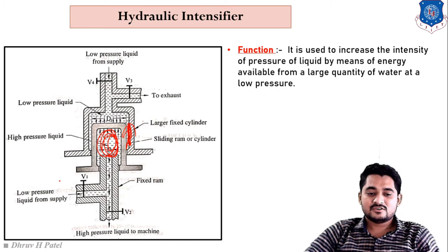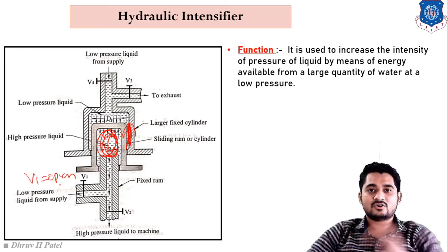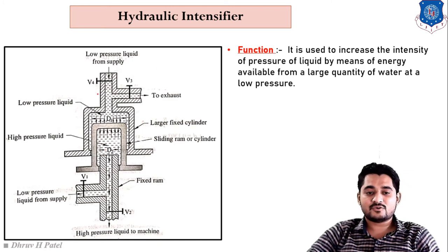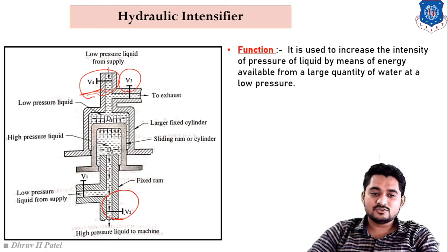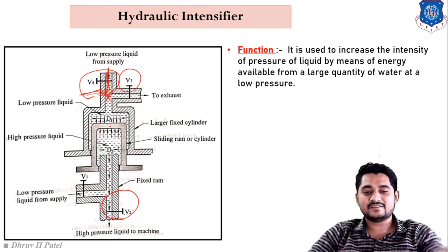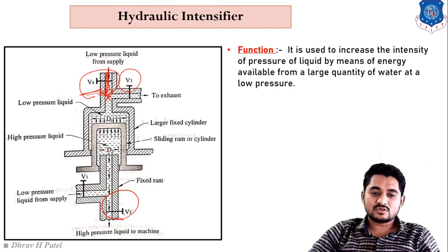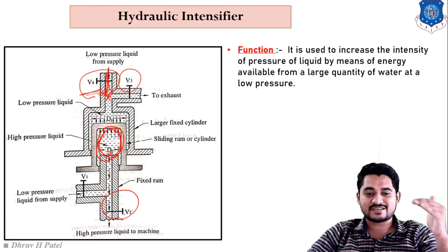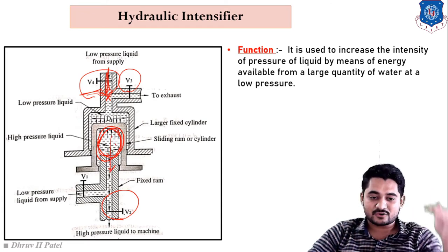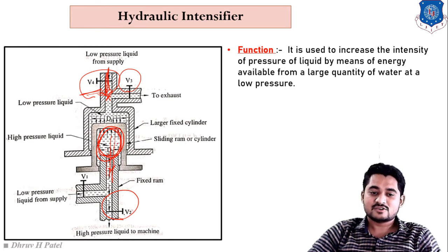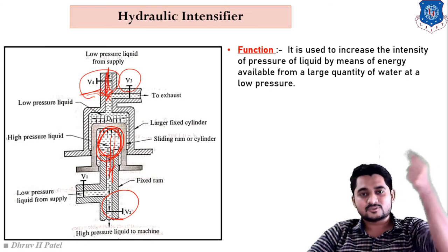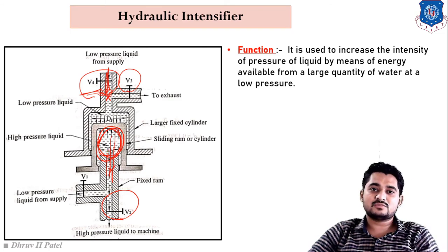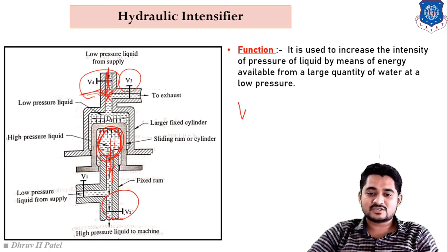Next, V4 valve is opened while V2 and V3 are closed. With lower pressure applied from above, the sliding ram moves slowly in the downward direction. The liquid stored in the sliding ram section moves downward into the fixed ram's smaller cross-sectional area — so the liquid moves from a larger to a smaller cross-sectional area, causing the pressure intensity to increase.